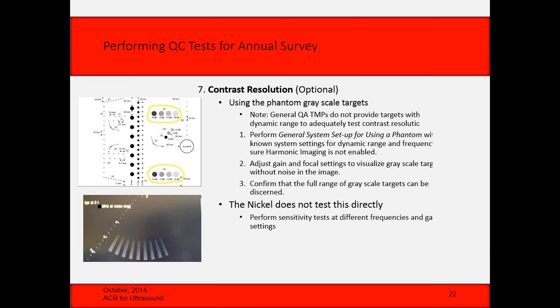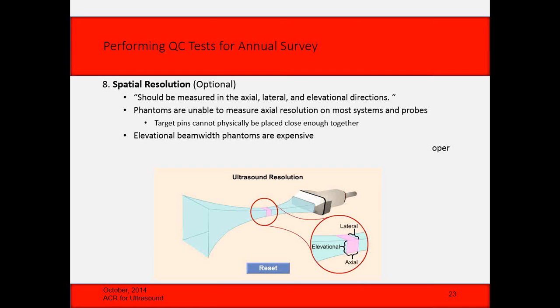So again, if you go to the absolute lowest frequency for that probe, at least you have a chance of seeing something if it is going wrong. And then the elevational beam width phantoms are kind of expensive. There is a way to use a general QA phantom and do an estimation of the elevational beam width. There's a white paper that a medical physicist wrote on this that's available that you can use to try to do that. And elevational beam width is not always controlled that well by the manufacturers. They have to make trade-offs in the resolution, and elevational beam width is one of the ones they sometimes trade off. The elevational beam width will start deteriorating pretty quickly when you have dead elements or elements that aren't working or channels that aren't working.